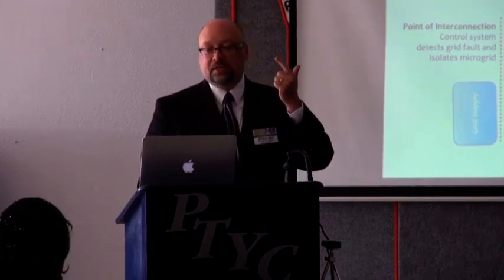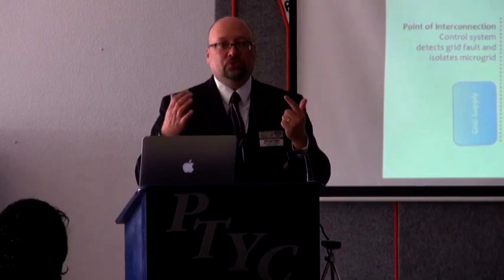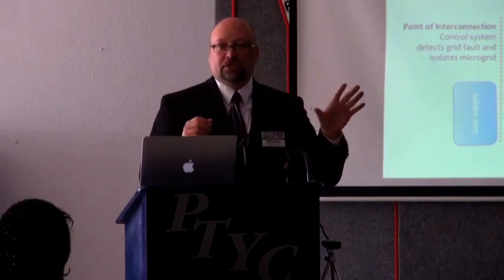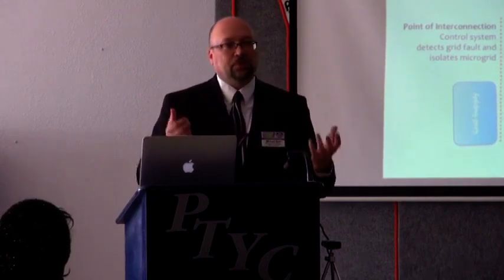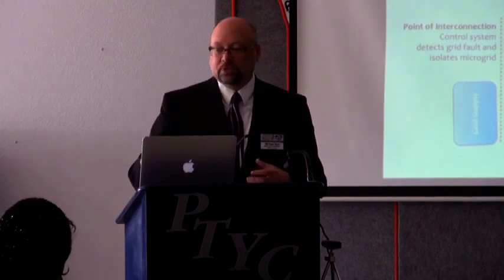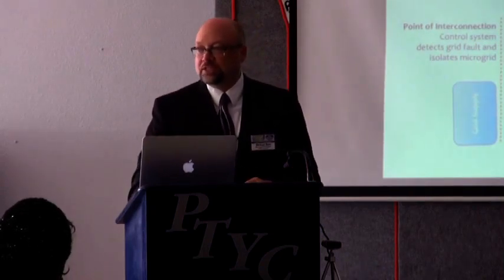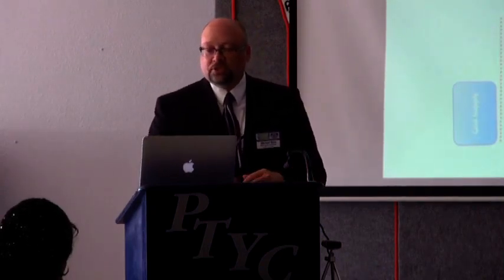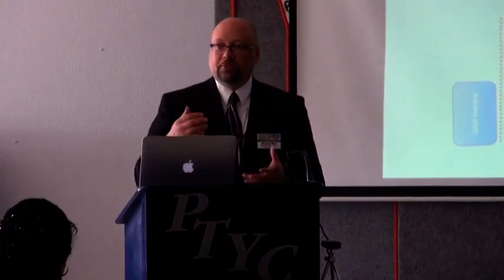The second thing it does is react to an imbalance, because if it lost the grid, it doesn't have enough supply to meet the load that was being served at the time. So what does it do? It may be able to shed some load—you can see the optional load dropping off. The microgrid controller will shed the load that's optional, that doesn't absolutely have to be served.